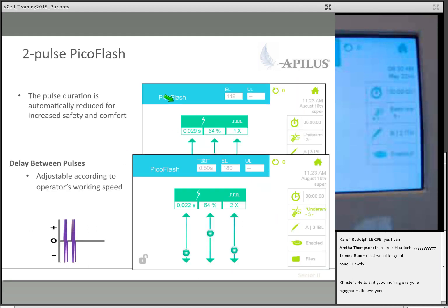So doing 2 pulses, here's our Picoflash screen again. And this is the settings when we have 1 pulse only. So with an underarm 3, for example, we have 0.029 seconds at 64%, 1 pulse. When we set it up, and here's our energy level, 119. If I were to do a double pulse manually, that means that I am pressing on the foot pedal twice with my foot. What happens is that I have to double this time and intensity, this energy levels. I would be delivering about 240 energy levels.